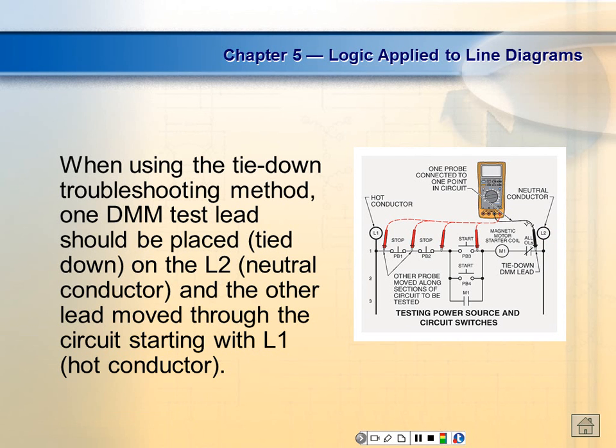And what are we looking for? Voltage. As soon as you find the voltage, whatever you just went over is the problem that's keeping that relay from energizing. If you measure right here and you measure approximately 0 volts, you move over here and you have 120 volts, then by George, you just found the open. It's the coil that's bad, right? You understand?